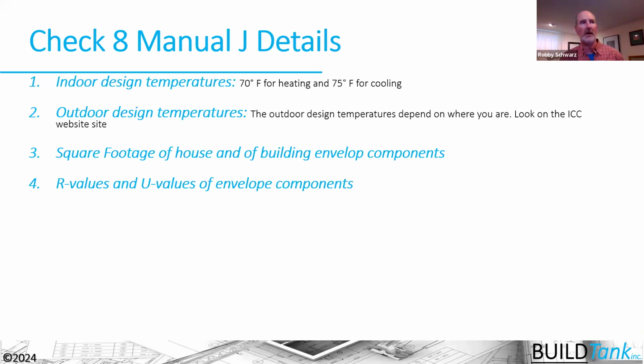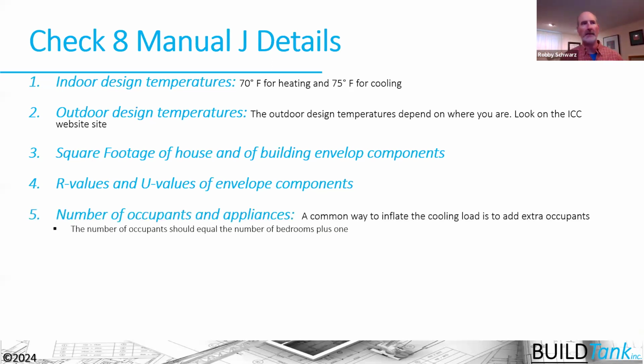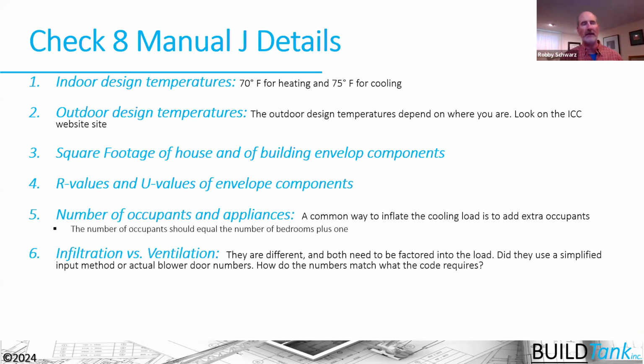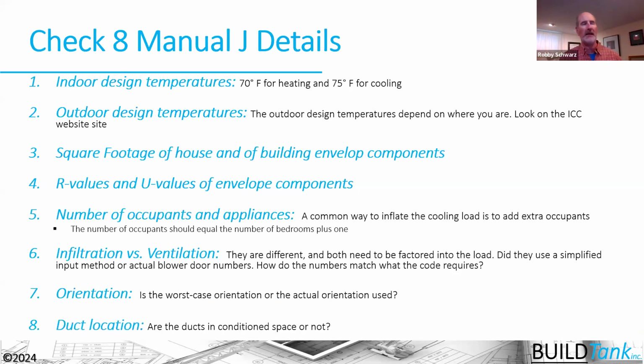We need to understand what R values and U values the envelope components are being entered with, and how they relate to what's being proposed in that system. The number of occupants and the number of appliances can change the loads for that house as well. And then obviously we've been talking about infiltration and ventilation and the loads that are associated with that. So I'll show you where you can find that information. Orientation of the house can make a big difference on the loads, specifically and more importantly with the cooling loads than the heating loads of the house. And then duct or piping or other distribution systems location can impact things as well.